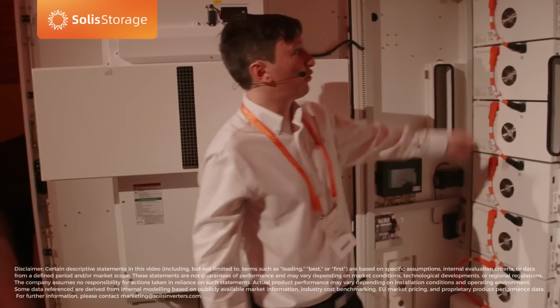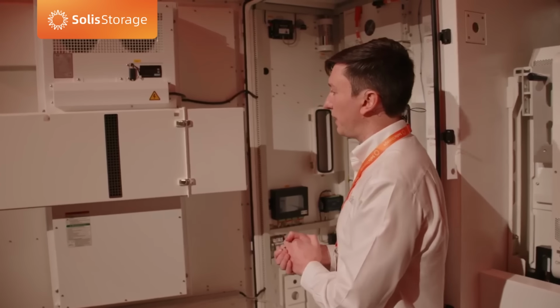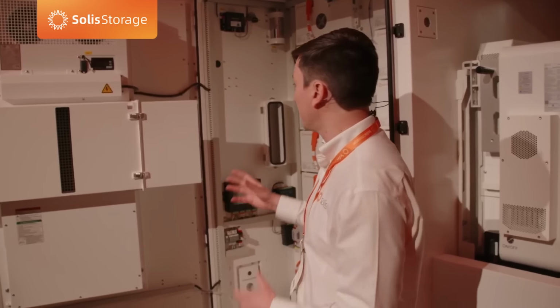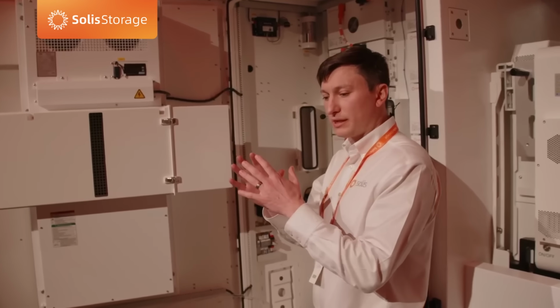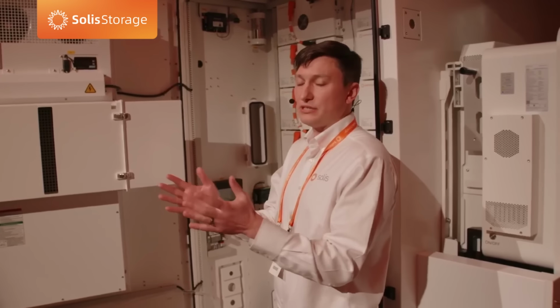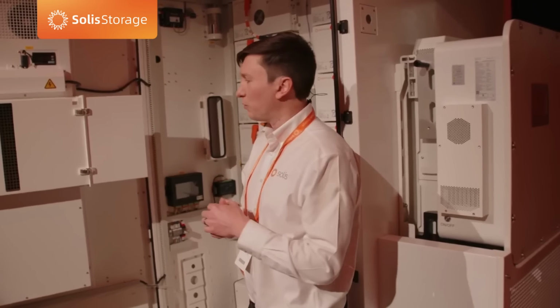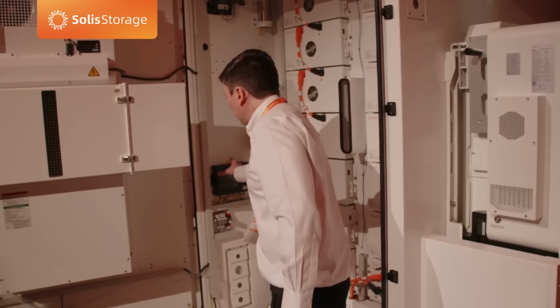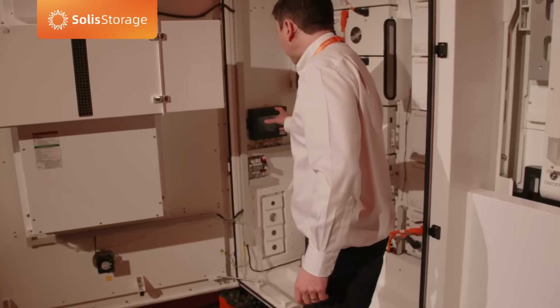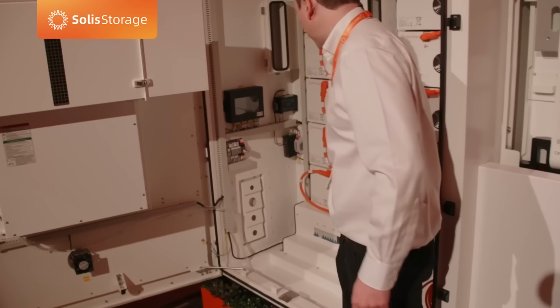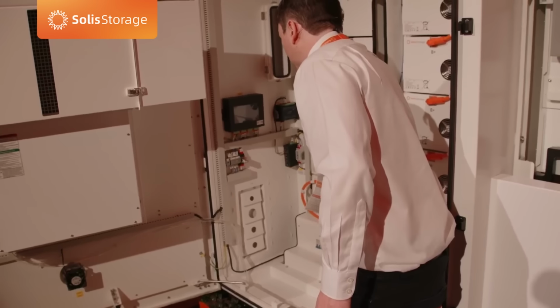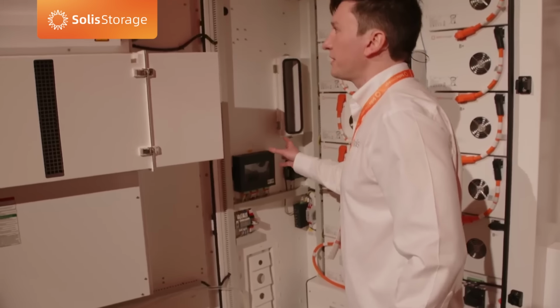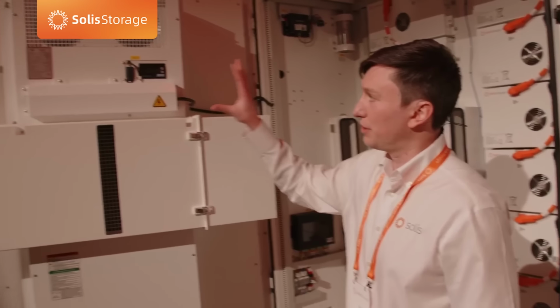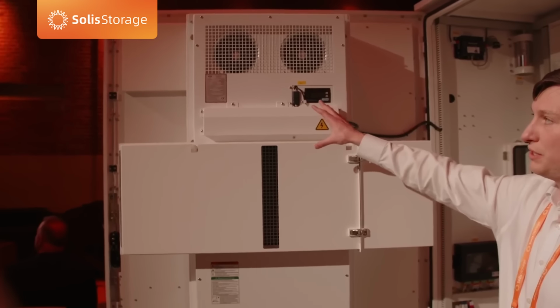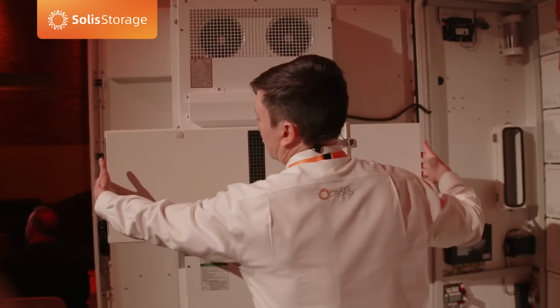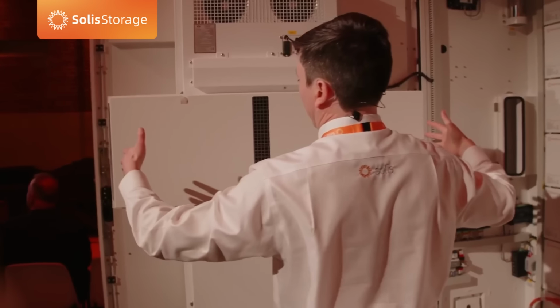That brings me to my third core element: thermal management inside this cabinet. With lithium batteries, we don't always need to cool it down - quite often in winter we actually need to heat it up. So what the EMU, the energy management unit, will do is detect a low temperature state on one of the cells inside the pack, and it will make the clever decision to fire off a control command to the air conditioning unit, which can heat and cool, to then turn on and shoot hot air out of the cabinet in the case of winter.